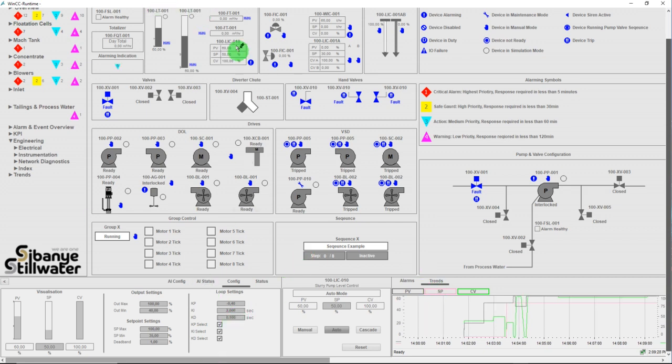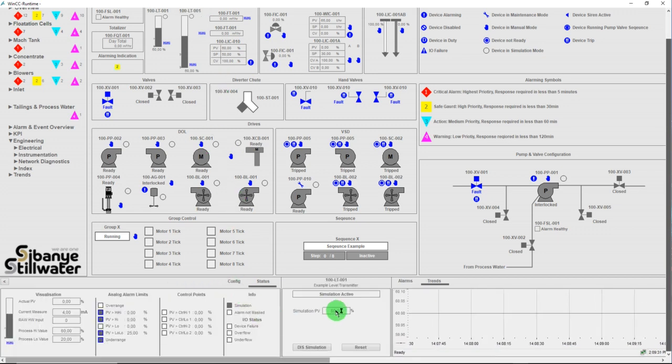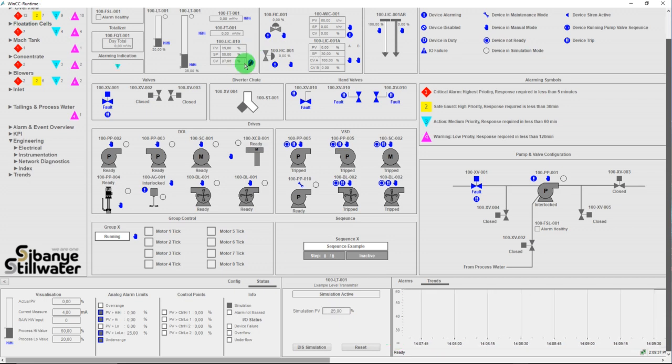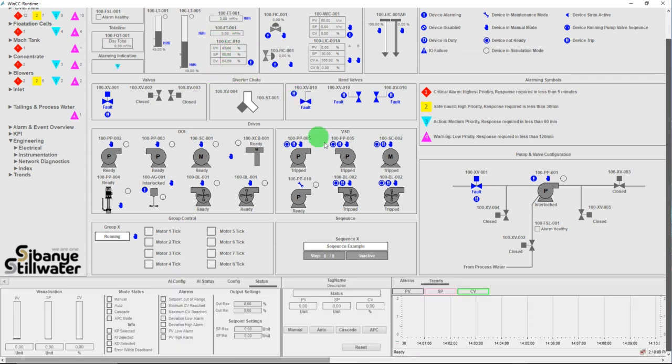With that being in now, if your plant is running, your variable will start to go up and down. And there I can see already with my tuning parameters that my control variable is going off fairly slowly. Let's say I take it up a notch. Here it's going to go down, and you can see that it's really attempting to control it. Now I've put the PV quite close to that, and because it's within a deadband, it's going to keep it static in that position.